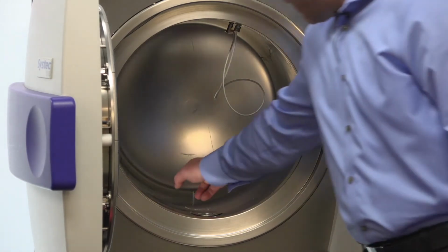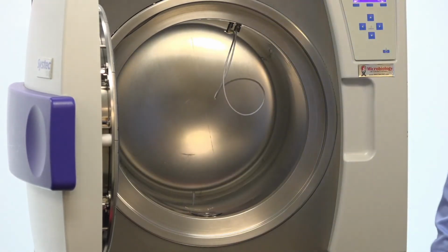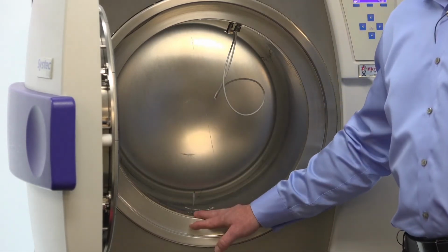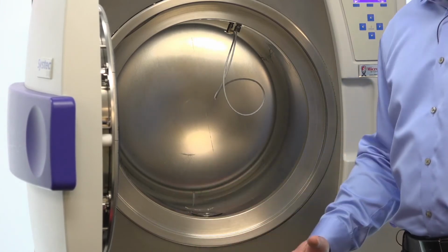So we have a probe directly in the back that is going to indicate whether we have any moisture or any water inside of the instrument. So if a cycle does fail because of power or something like that during the cycle, it would indicate that to us, so we are never able to open the door and have all the water flow out onto us.